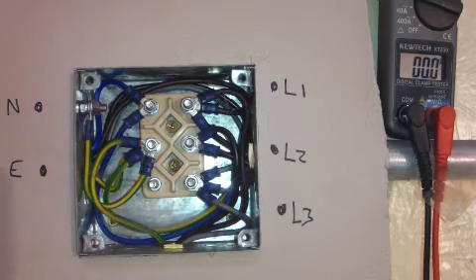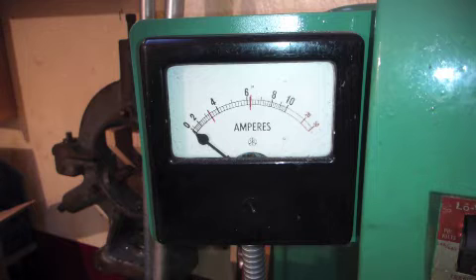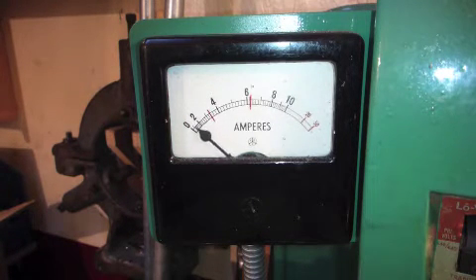Let's look at the currents we're getting now. If you do put a spindle ammeter on your machine, I've got one on my most frequently used machine, it's important to make sure that it is actually on the strongest phase. And the strongest phase may not necessarily be the one which is true live after you've added the capacitors. So it's important to check. But in starting this you can see why you really can't use that normal kind of multimeter to determine the current. Because it'd make it go bang.